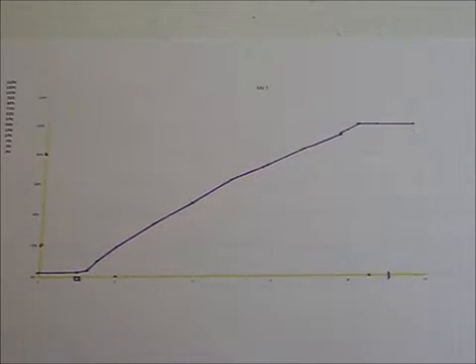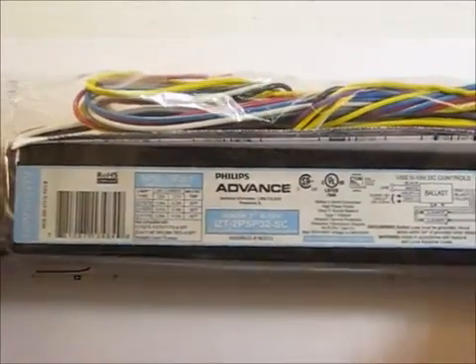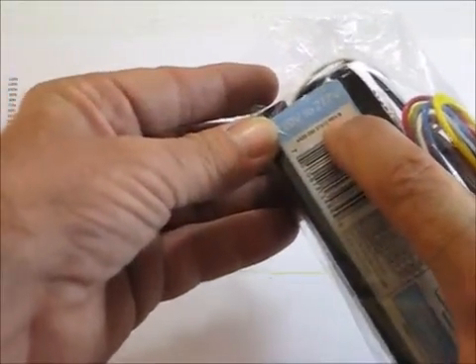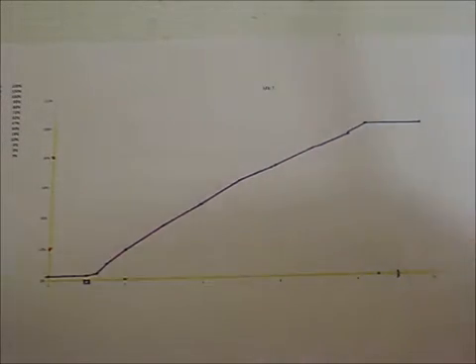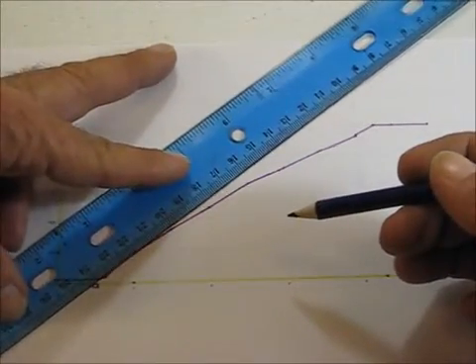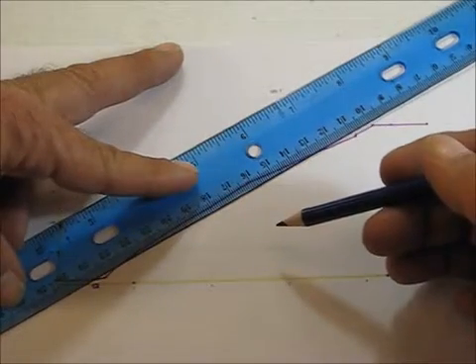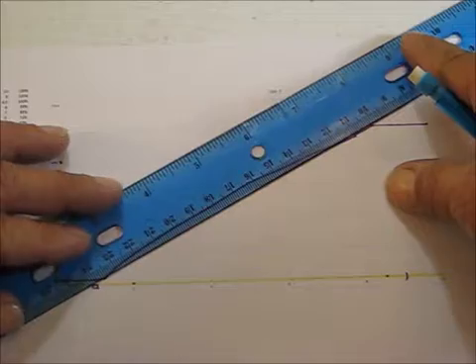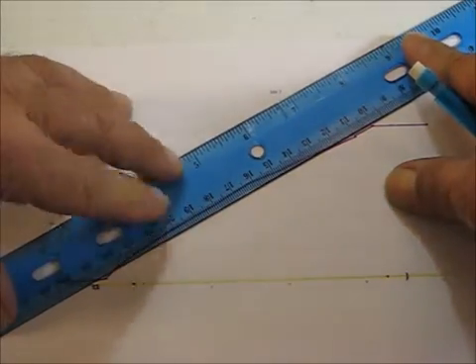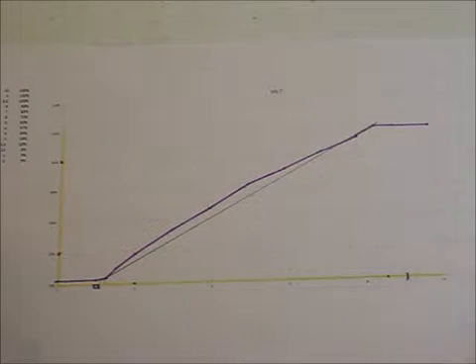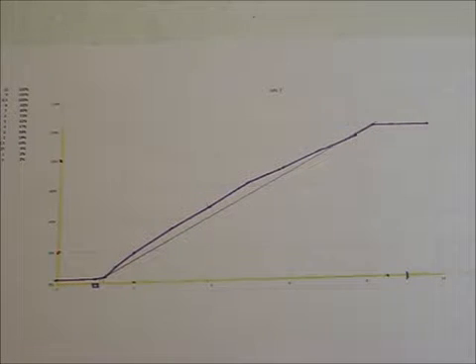Okay, let's analyze the data from this Philips Advance Mark 7 0 to 10 volt dimming ballast IZT-2PSP32-SC. It's definitely different than the first one I looked at. This one says Revision B on the sticker. And it's practically a straight line between 8.5 and 1.5 volts. That's, even with our crude little analysis that we're doing today, that is pretty freaking good. Which makes this thing suitable for open loop daylighting.